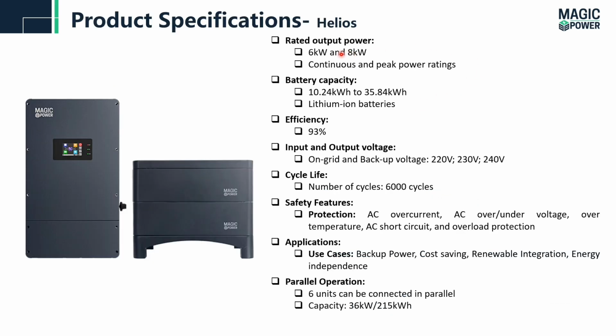The product specification: rated output power 6 kilowatt and 8 kilowatt, which are the continuous and peak power ratings. Battery capacity ranging from 10 kilowatt hour to 35 kilowatt hour. Each battery module in this system is 5 kilowatt hour. The cell technology is lithium ion batteries. Efficiency is 93%. If we talk about the voltage, that depends on the grid standards, which could be 220, 230, or 240. And similarly, the frequency could be 50 or 60 hertz.